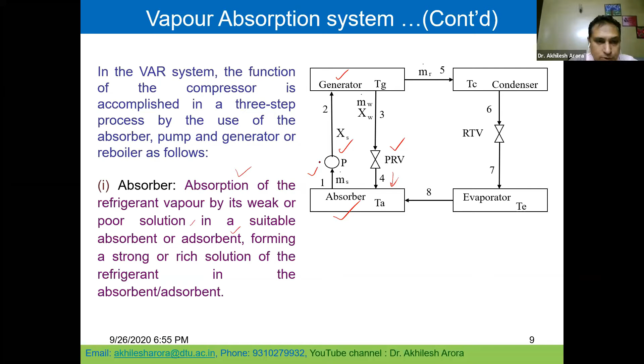Now let us see the function of the pump. Pump is utilized for pumping the rich solution. Here we have the rich solution of the absorbent and the refrigerant, and it increases its pressure to that of the pressure which is existing in the generator. And what we do in the generator? In the generator, we carry out the distillation of the vapor from the rich solution, leaving the poor solution for recycling. So basically what we are doing, we are supplying heat at this particular point.